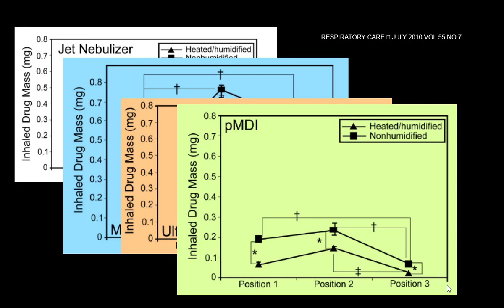So put it in the inspiratory limb. If you are using a jet nebulizer, please be as close to the ventilator circuit as possible. Otherwise, you are losing a lot of drug. If you are using ultrasonic or mesh, it should be in the inspiratory limb 15 centimeters away from the Y junction. There are certain studies where they have placed the mesh nebulizer, especially when you are using a heated humidifier, between the humidifier and the ventilator, which means you are as close to the ventilator as possible. There's no problem using this, but make sure that when you are nebulizing, switch off your heated humidifier. Otherwise, the entire idea of using a vibrating mesh nebulizer over an ultrasonic nebulizer is lost if you are heating your drug.